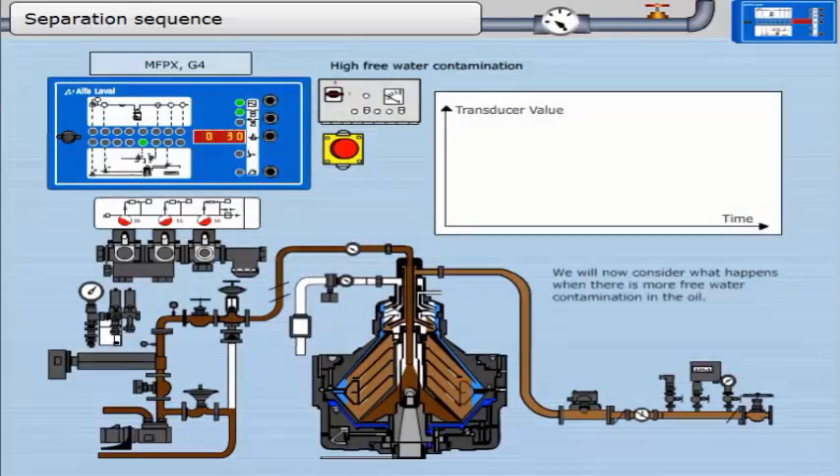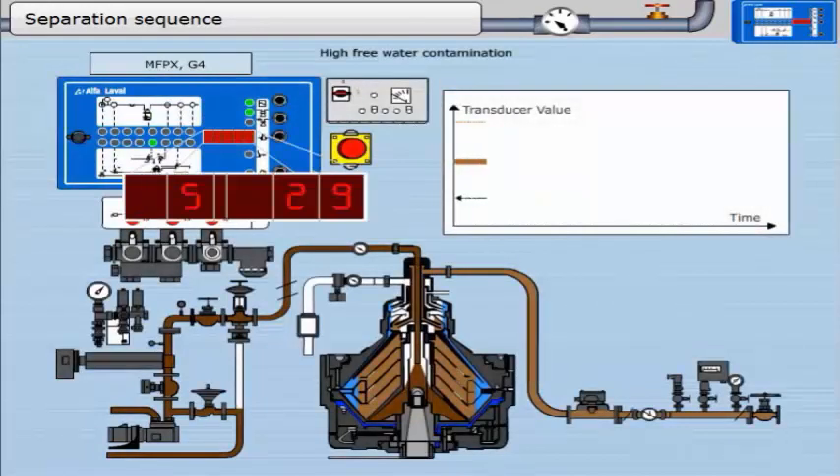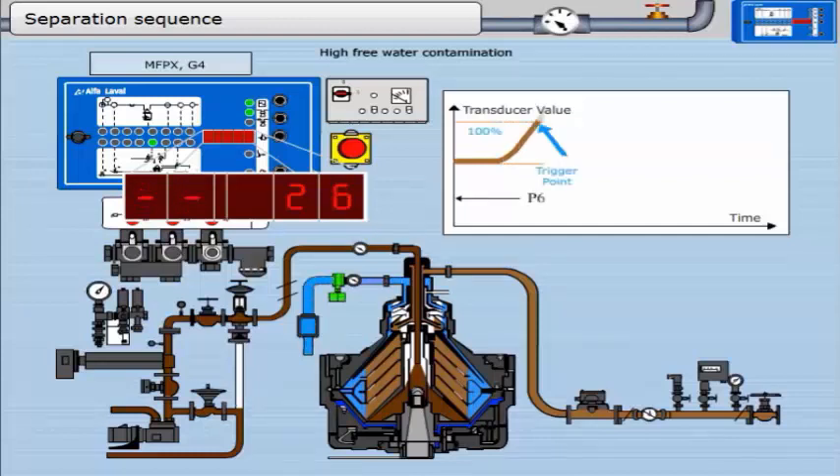We will now consider what happens when there is more free water contamination in the oil. The first part of the separation sequence is parameter P6; this timer runs for 10 minutes. As the water fills inwards, the graphical transducer value should increase to the trigger point. When the trigger point is reached, the water level in the bowl has reached the disk stack. The water drain valve opens and water leaves the bowl slowly through the hole in the flow control disk. There is a slight drop in oil back pressure when the water drain valve is open.